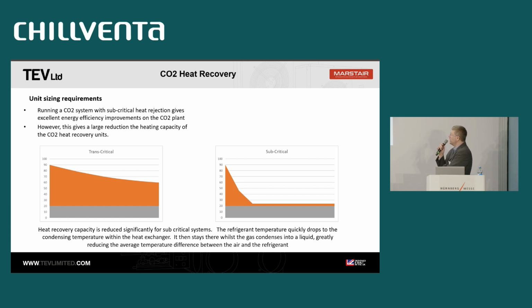What you'll see is that the orange area of the graph is the amount of actual cooling duty that you're doing. That would be kilowatts in terms of the total area. Now, when you go subcritical, a whole load of energy is required for changing the gas into a liquid within the heat exchanger. So you lose a whole load of the potential duty that the cassette can do. Running a CO2 system subcritically is much more efficient for the overall system, but within an air conditioning cassette, you actually lose a lot of duty.